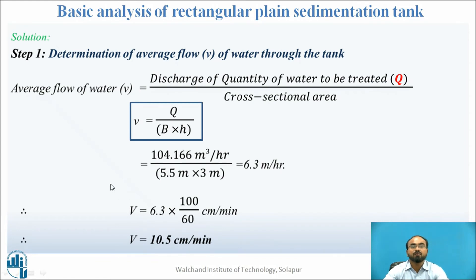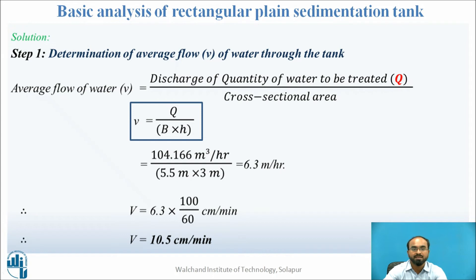First, the average flow rate: small v = Q divided by cross-sectional area = Q / (B × h) = 104.166 / (5.5 × 3) = 6.3 meters per hour. To convert to centimeters per minute, multiply by 100 and divide by 60. This gives the horizontal velocity as 10.5 centimeters per minute.